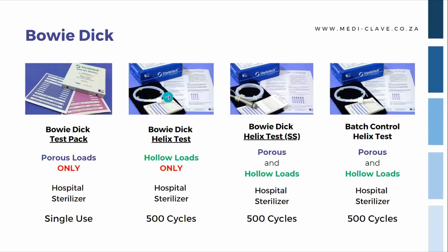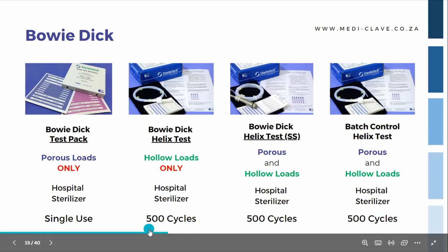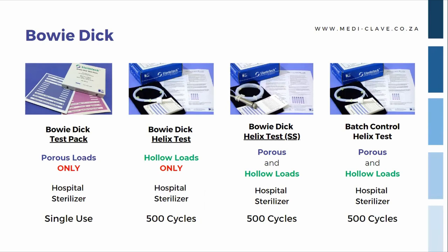And then the next one is the Bowie Dick helix test. It's for hollow loads only, also used in hospital sterilizers, and it can be used for 500 cycles. I just want to, before I carry on with the rest, clarify that the 500 cycles is your PCD and your indicators. Your indicators are 500 indicators, and they are placed into your PCD. So your PCD can only be used for 500 cycles.